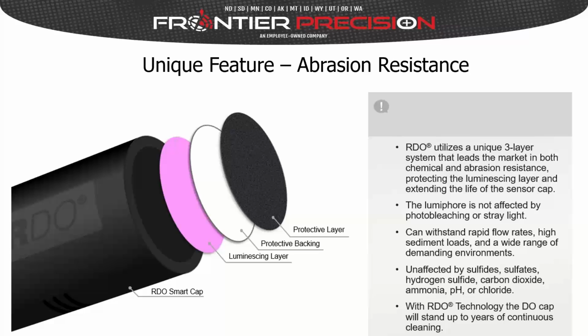In-Situ also uses the same sensor on our multiparameter probes, where we have a mechanical wiping system that's centrally located and it spins around and cleans all your sensors. And with some of our competitors, that frequent wiping of their systems will take this coating right off of that. Not so with our sensors. So again, it stands up very well with cleaning and high sediment across it.